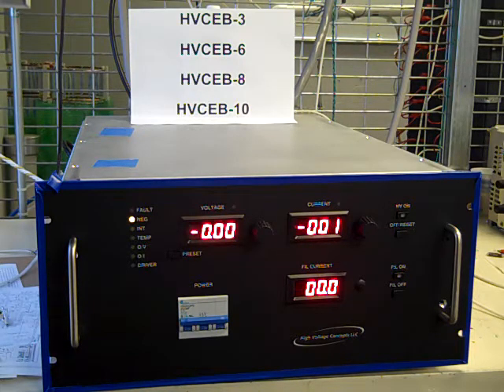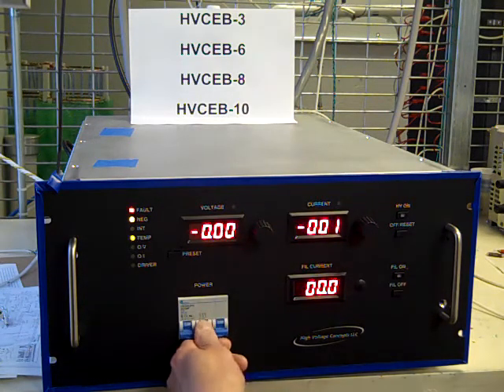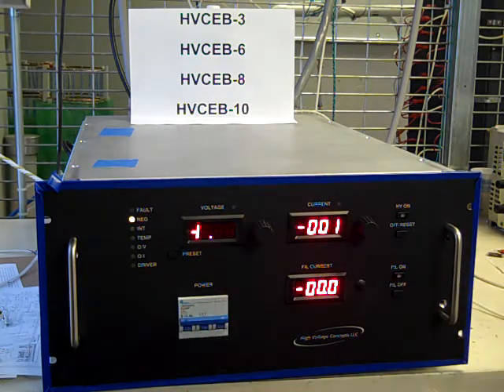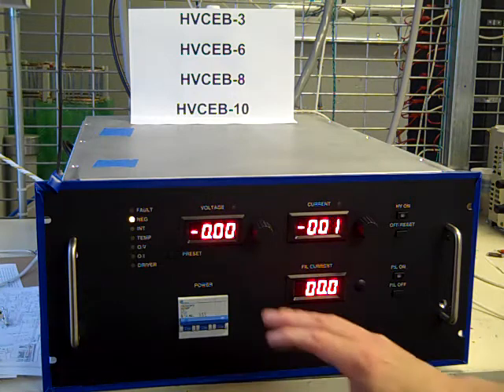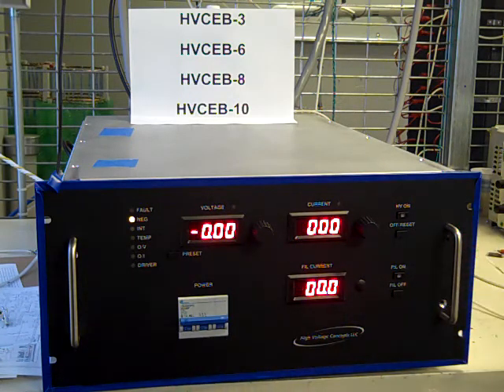The first two, the 3 and the dash 6, have flying high voltage leads. They could run 1 gun. Alright, today I'm going to show you the operation of this power supply, and we'll start off when the circuit breaker is turned on. Initially, for the very first time, there's approximately a 35-second delay for the driver to come up to power. Once the breaker's on, there's no delay for you to turn high voltage on.